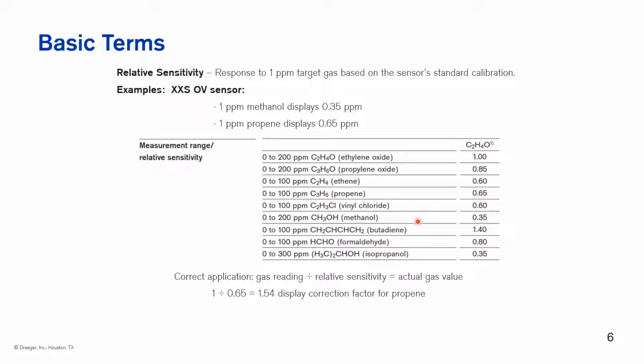So within our instruments, we can set it up so that we can calibrate with one gas, display another gas, and have a correction factor automatically applied. If you don't have that, you can use the relative sensitivity to do a calculation to get your actual gas value. So you take your gas reading, divide by the relative sensitivity to get your actual gas value. If you want to calculate a correction factor, you can take the one reference from the ethylene oxide, in this case propene, the 0.65. So you take 1 divided by 0.65. That gives us 1.54. That would actually be our display correction factor for propene. So you'll find this on, like I said, on a number of our sensors, just depending on what the application may be.